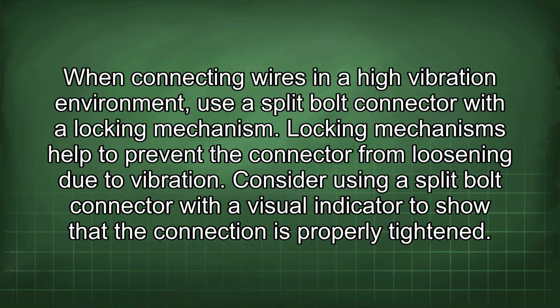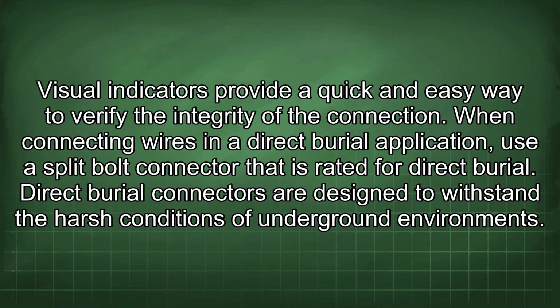When connecting wires in a high vibration environment, use a split bolt connector with a locking mechanism. Locking mechanisms help to prevent the connector from loosening due to vibration. Consider using a split bolt connector with a visual indicator to show that the connection is properly tightened. Visual indicators provide a quick and easy way to verify the integrity of the connection.